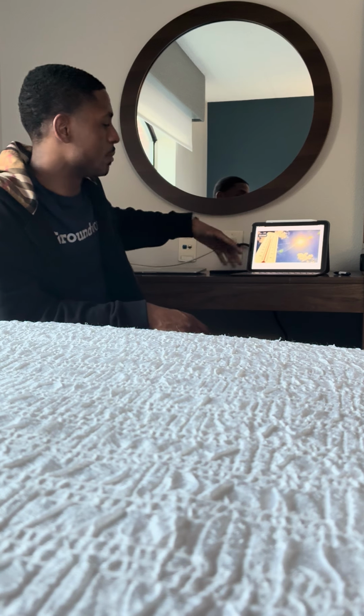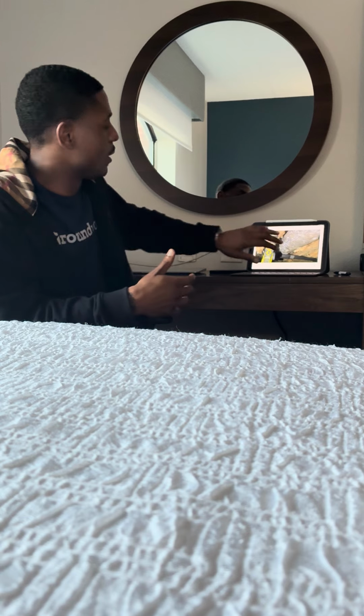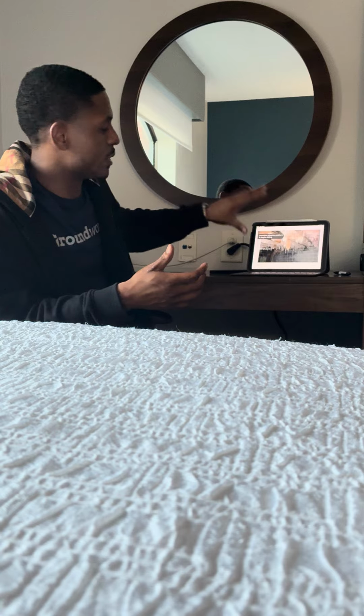Now, in the summertime, you're going to have more moisture in your air. That's going to go straight to your floor framing system. That's going to absorb that moisture from that warm air. Now, when that warm air clashes with that cold air down in your crawl space, then that's when you're going to start to see the condensation come in. That's going to start to saturate your floor framing system and go directly into your insulation.